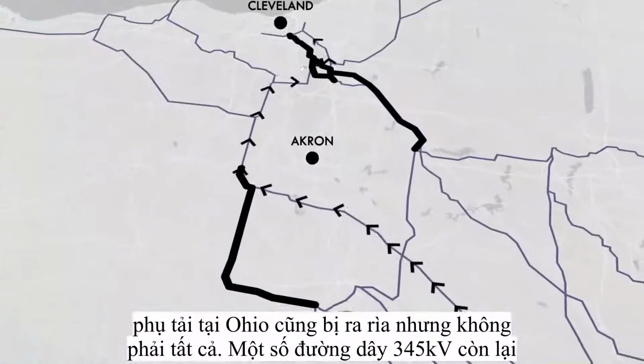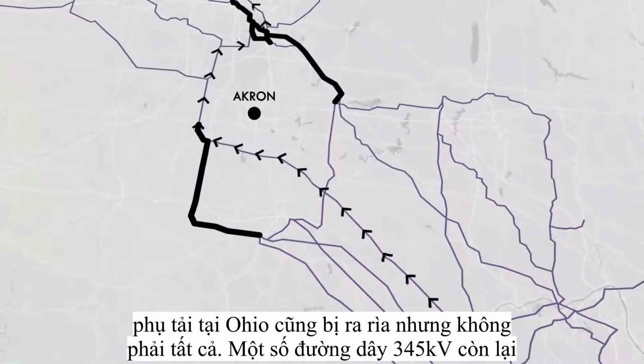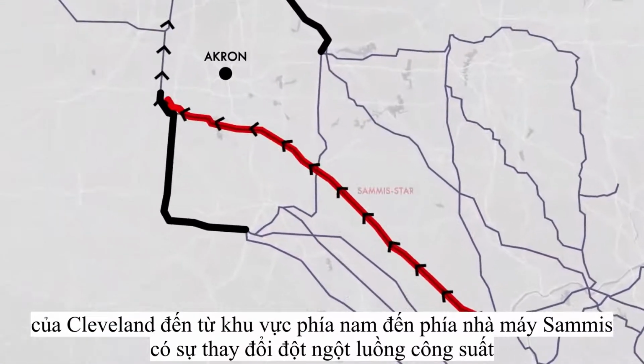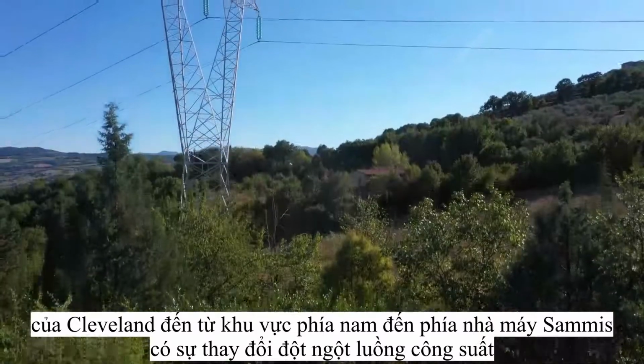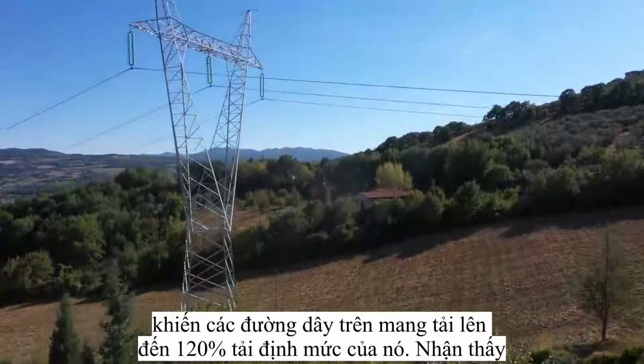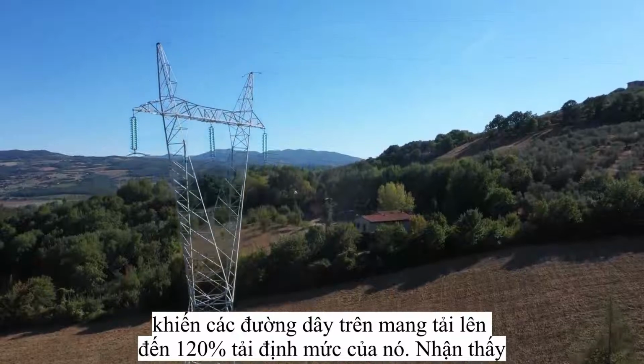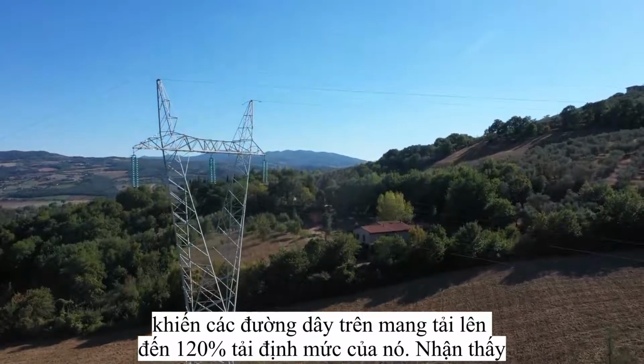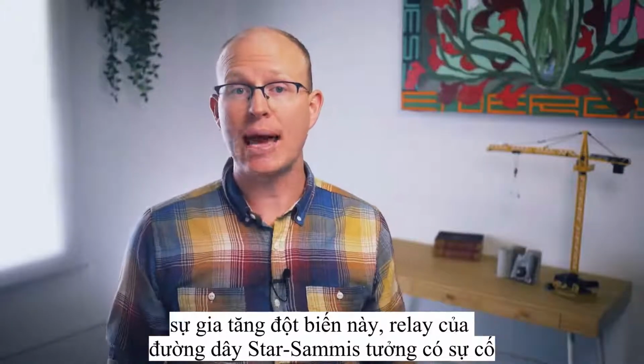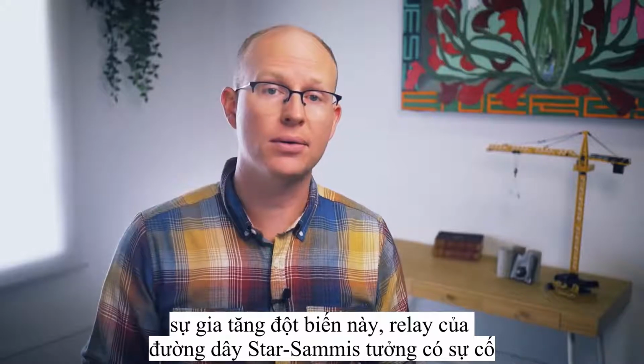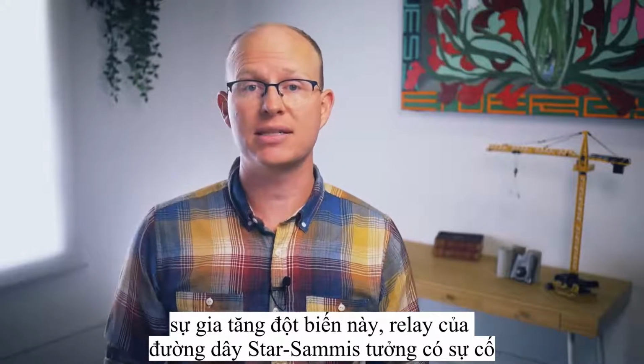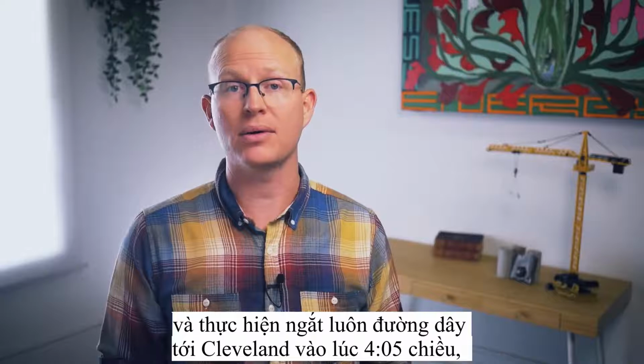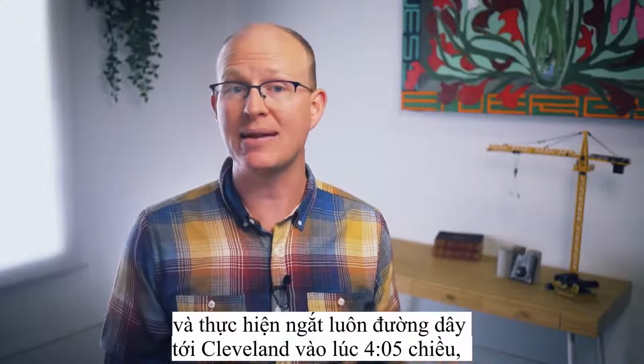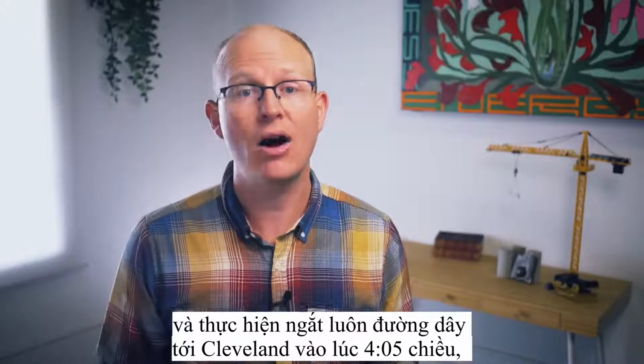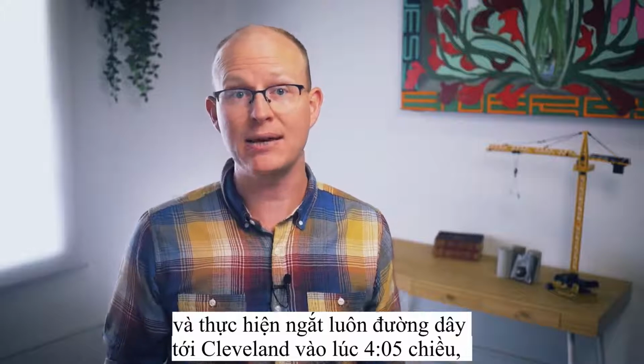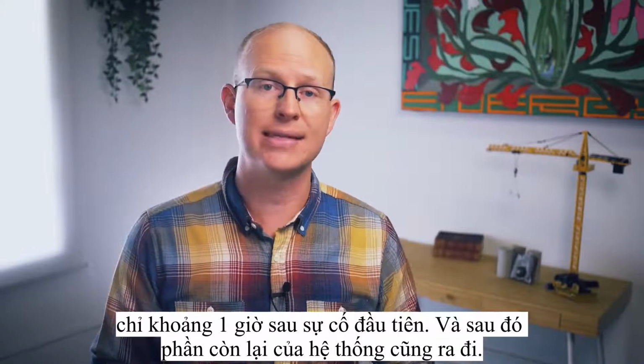The last remaining 345 kV line into Cleveland from the south came from the Sammis power plant. The sudden changes in current flow through the system now had this line operating at 120% of its rated capacity. Seeing such an abnormal and sudden rise in current, the relays on the Star-Sammis line assumed that a fault had occurred and tripped the last remaining major link to the Cleveland area offline at 4:05 p.m., only an hour after the first incident.